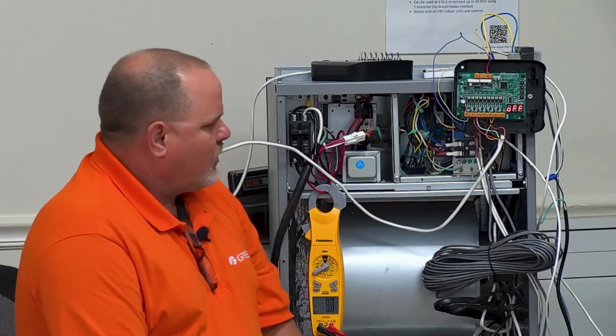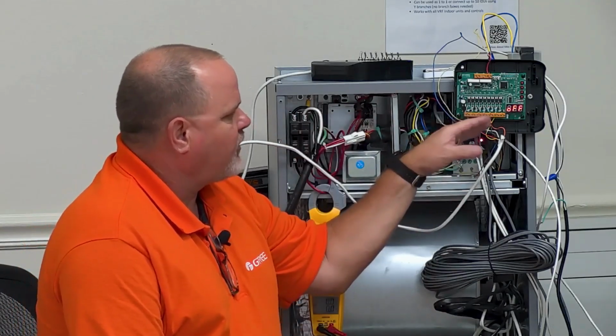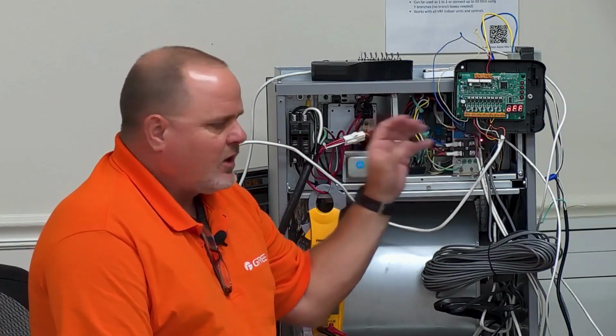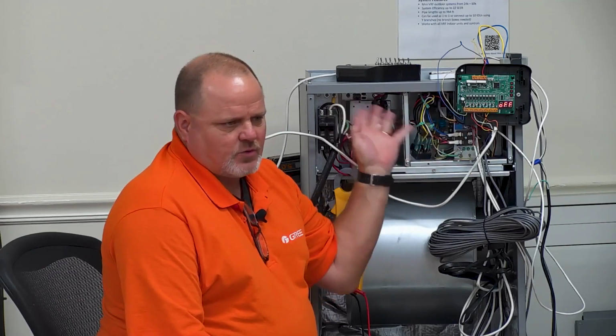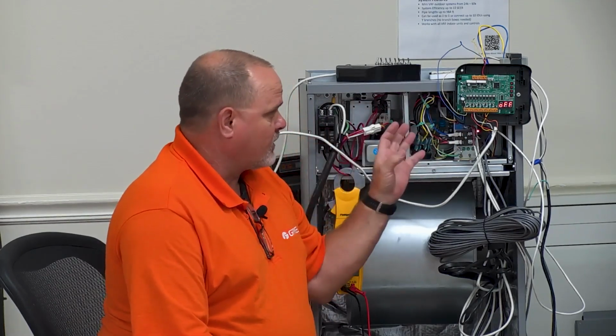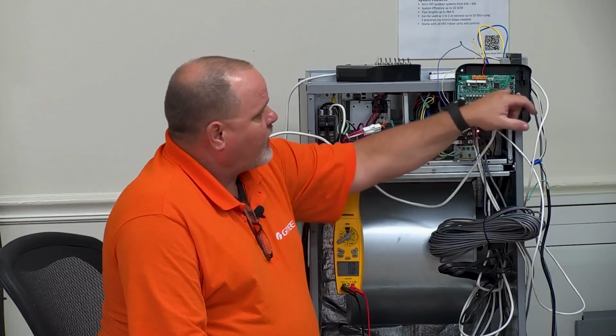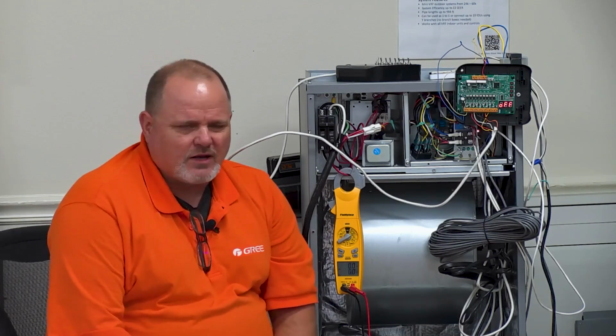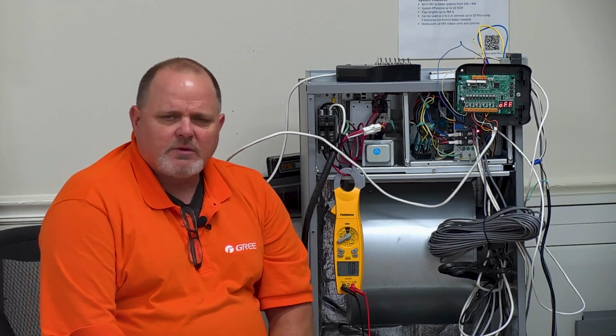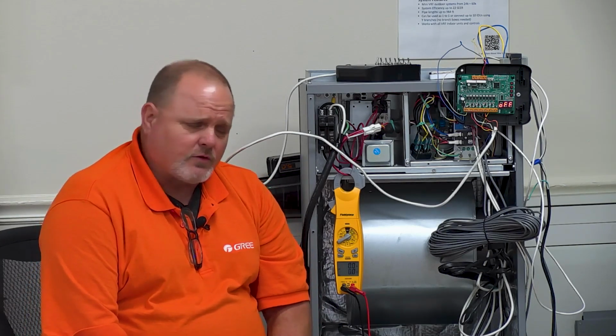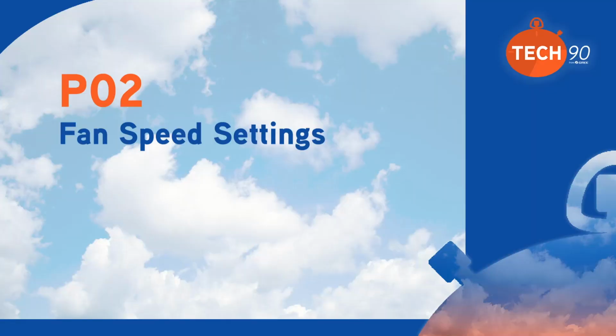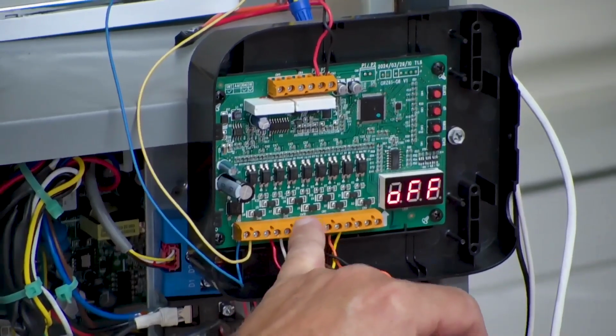So I have one all wired up here with my thermostat wires and everything in front of it. You guys really can't see the terminal designations. That's why I was using the other one to show you what the terminal designations were. Over here on the right-hand side, we have the red buttons. So that's where we get into P codes. And I don't expect you guys to remember all this. It'll be in the instruction manual that comes with the 24-volt adapter. So without further ado, we'll talk about P02 first, which is our fan speed settings. So if we're going to wire to G only, then you would set the P02.